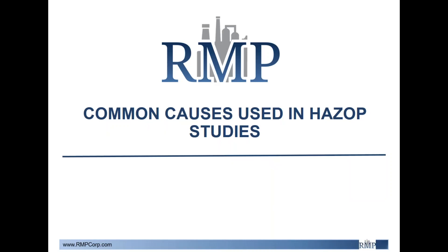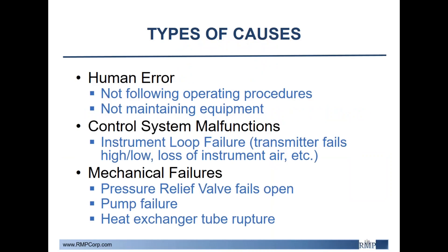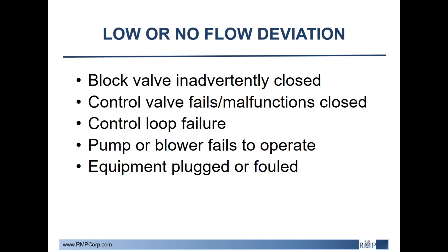Now I'll begin discussing the common causes in HAZOP studies. There are several types of causes to look out for. One would be human error, such as not following operating procedures — for example, an operator inadvertently opening a valve or not maintaining equipment and allowing things to foul. Another type is control system malfunctions, like instrument loop failure, which could be transmitter failure or loss of instrument air. And finally, mechanical failures are also very commonly seen, such as pressure relief valves failing open, pumps failing to operate, or heat exchanger tube ruptures.